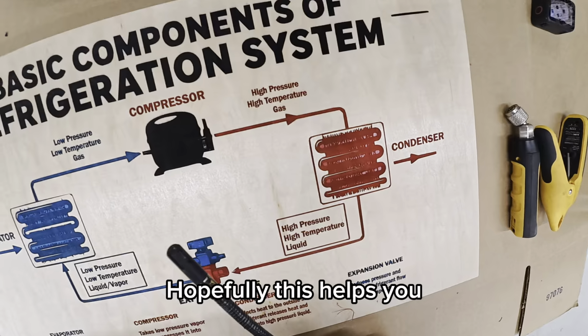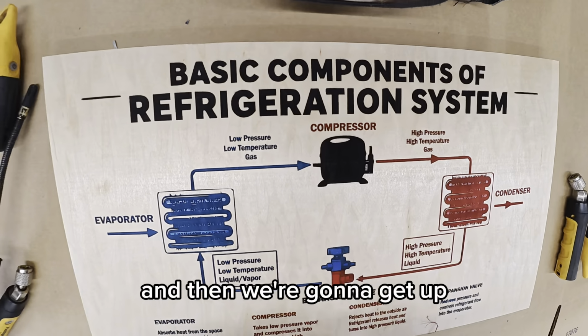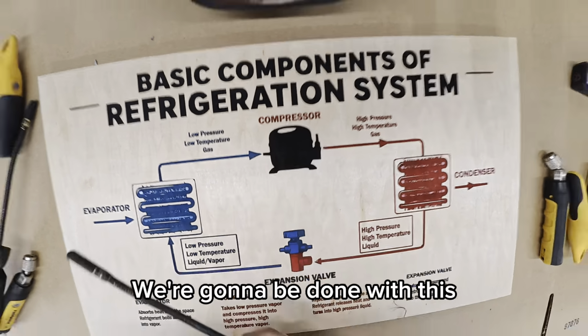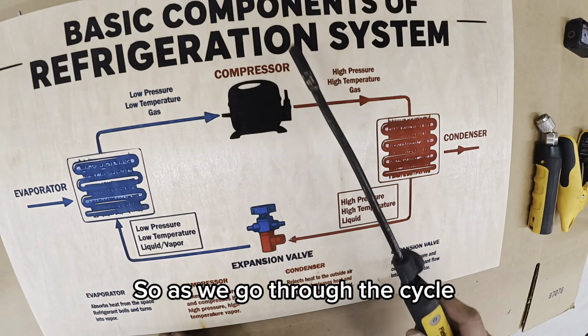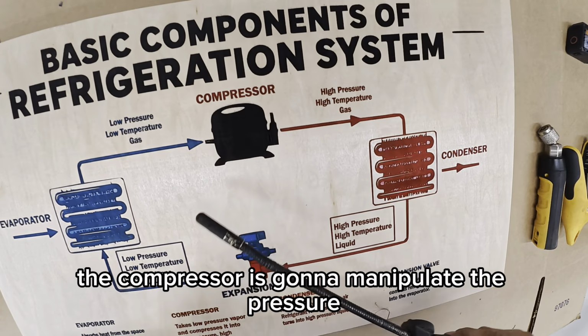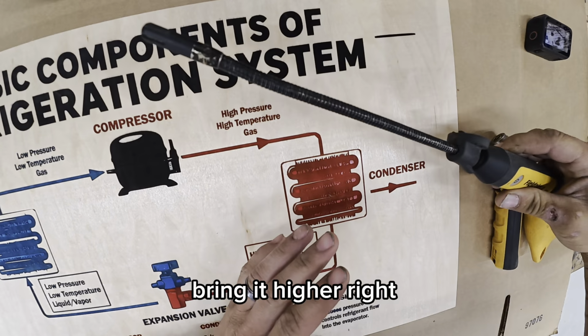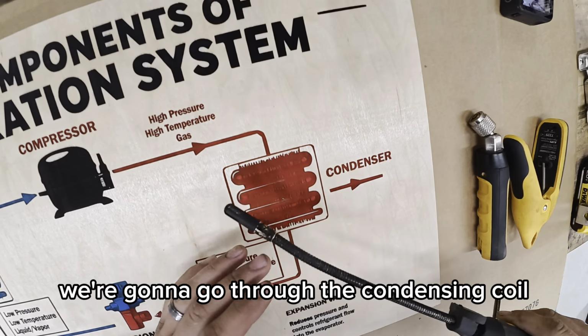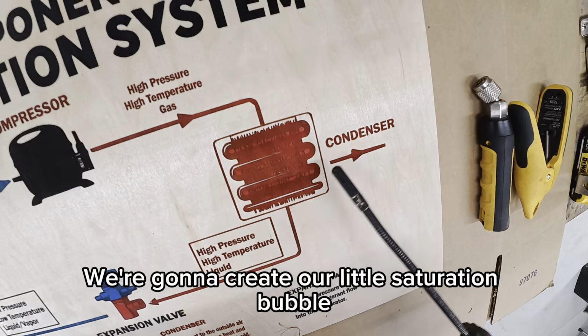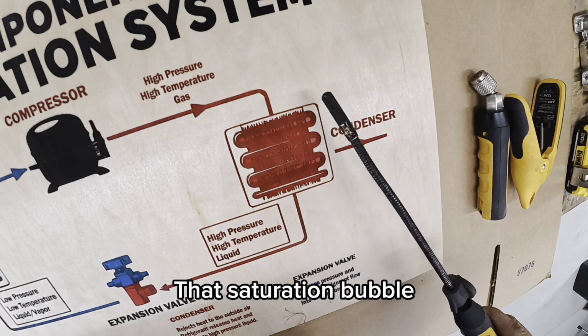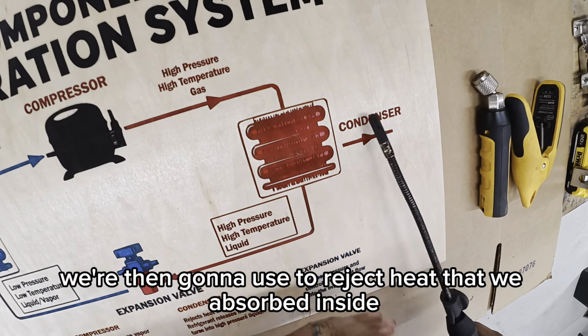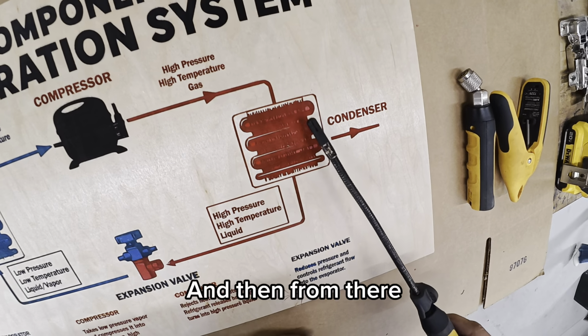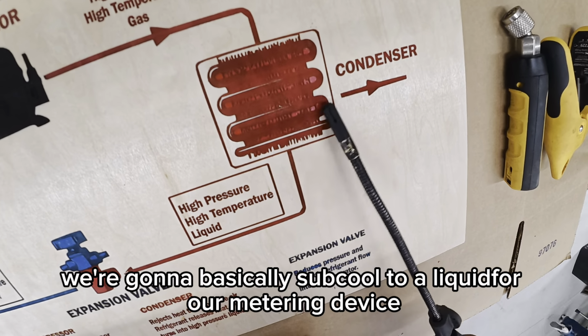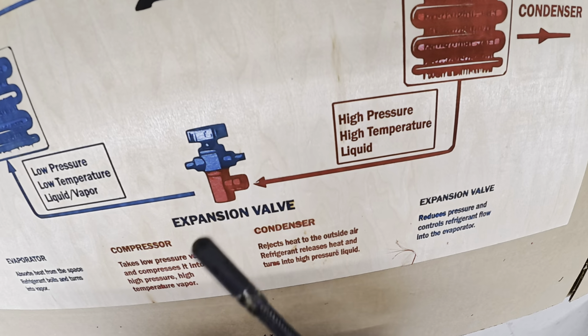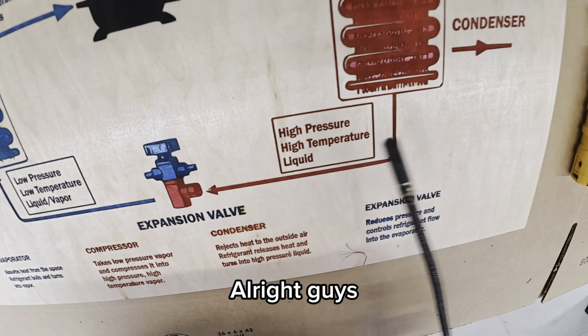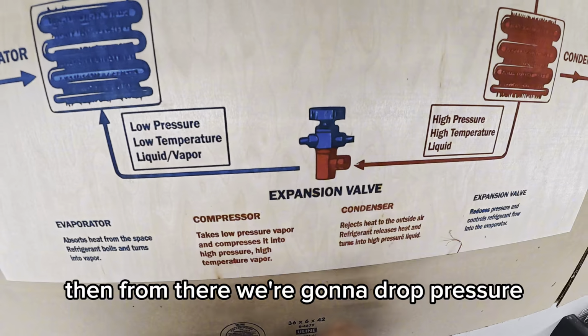So hopefully this helps you. Let's go over it one more time, guys, and then we're gonna be done with this. As we go through the cycle, the compressor is gonna manipulate the pressure, bring it higher, right? We're gonna go through the condensing coil. We're gonna create our little saturation bubble. That saturation bubble we're then gonna use to reject heat that we absorbed inside. And then from there, we're gonna basically subcool to a liquid for our metering device that needs liquid, all right, guys? Then from there, we're gonna drop pressure.